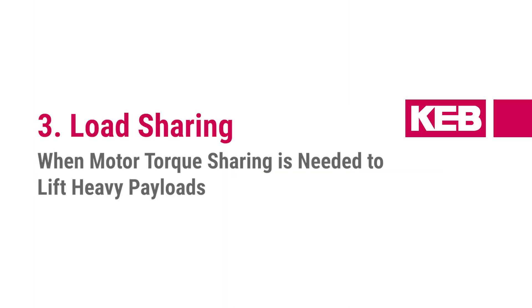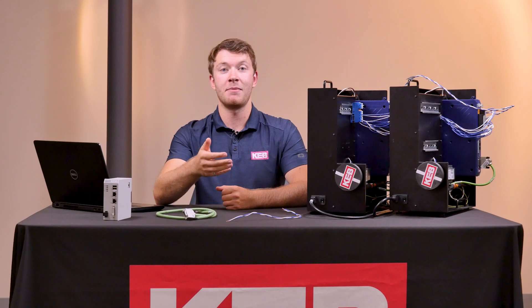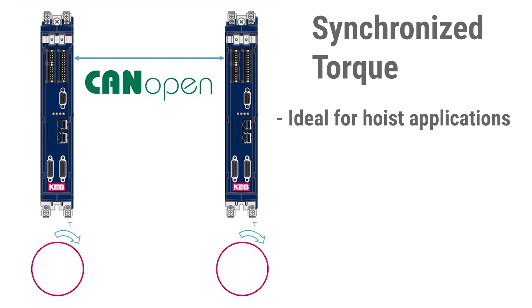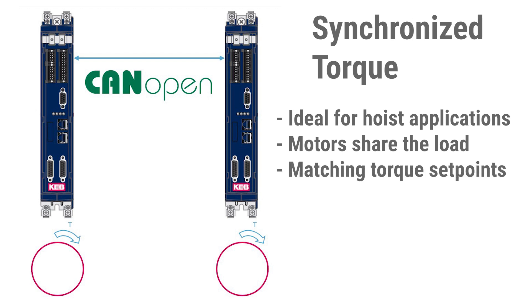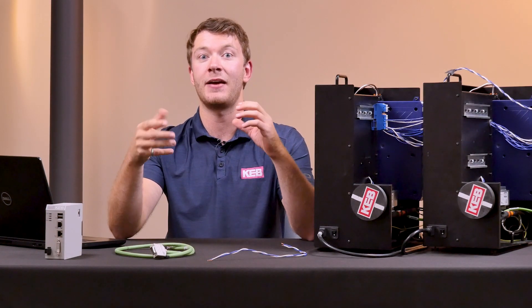The third type of master-follower is load sharing. This is when the torque of the master drive is sent to the follower drive. This is important for applications like hoists, where two motors run together and must share the load between each other. Torque set points have to match so the motors aren't fighting each other and can evenly distribute the load on a rigidly coupled shaft.